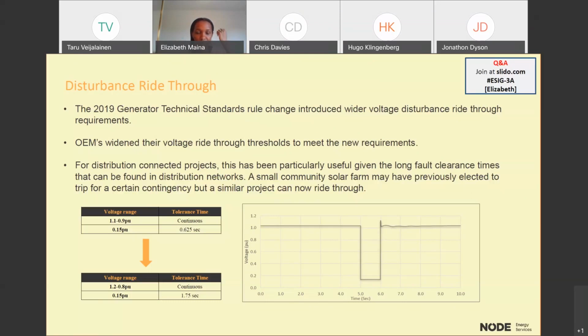A good example of that would have been a particular fault in the distribution network, which would have seen the voltage, looking at the little curve that I've got there, drop from 1.03 to 5 seconds. A fault happens and the voltage collapses to 0.15 and remains at that level for maybe 1 second before recovering. So a project previously that would have connected at that level in that distribution network would have had a protection setting that would trip it, so it would not be able to recover following that fault.